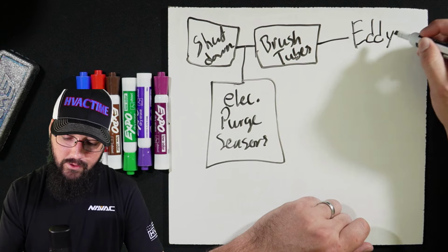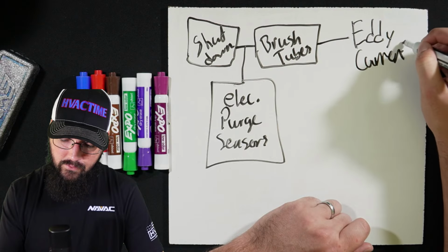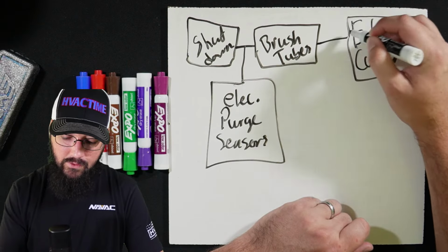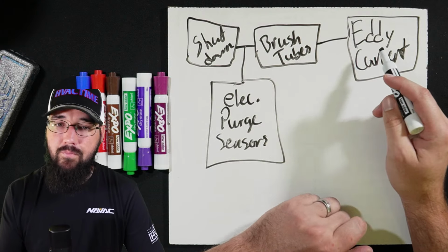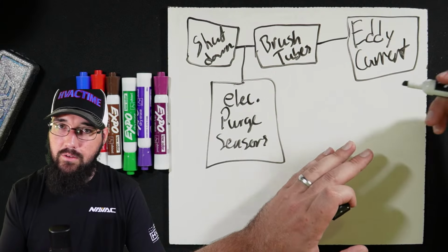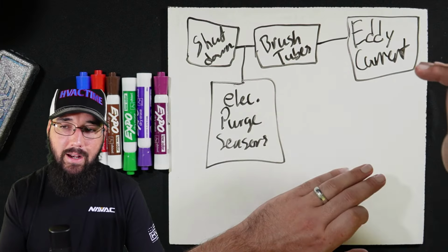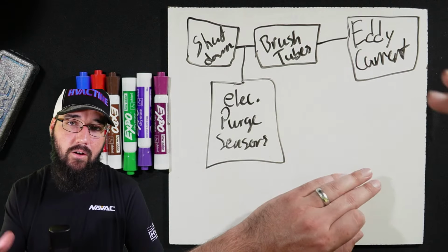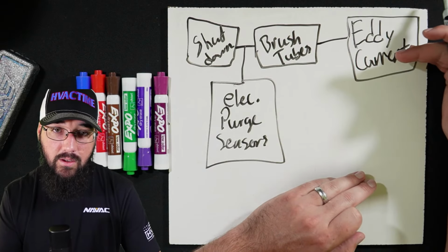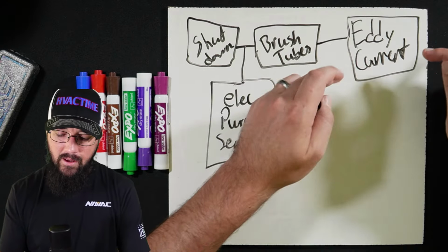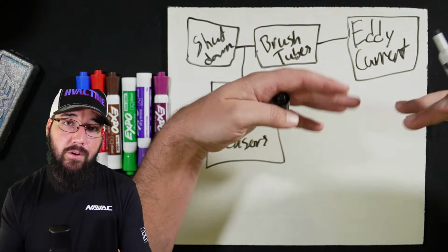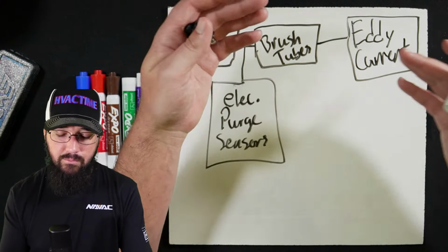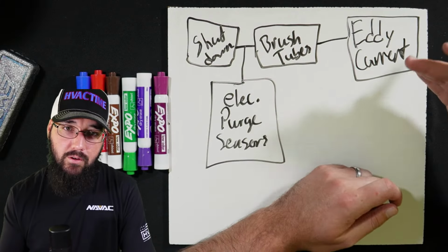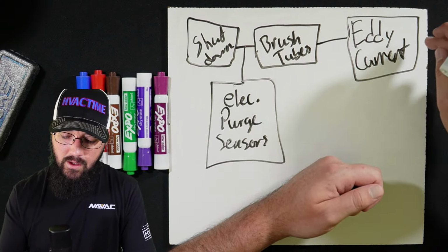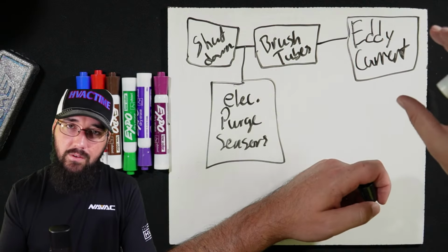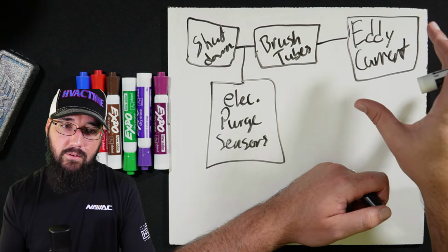So if we're going to do an eddy current, that's where this comes in. We'll have an eddy current tech come in and process both sets of tubes. If we've got to plug tubes, whatever the case, we'll handle that at this point, while he's there. Identify those tubes. If he recommends plugging, then we have to open up both ends of the barrel, which in most scenarios we don't need to do. But in this particular one, if we've got to plug a tube, we have to get to both sides. So that's working through the eddy current piece of it.